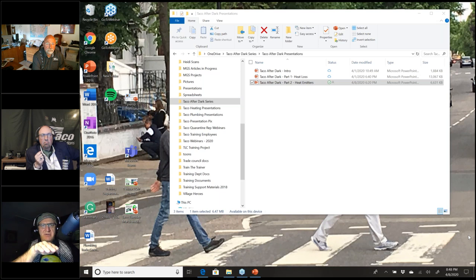These two down below require lower water temperatures. When those are running, they're sending the lowest possible water temperatures back to that boiler. That boiler is going to really like that, and it's going to be really efficient. So don't think, a lot of times people say, well, I'm using a mod con boiler, I'll just make everything the same temperature because it would be easier. Yes, it would, but there are benefits to resetting off the reset.